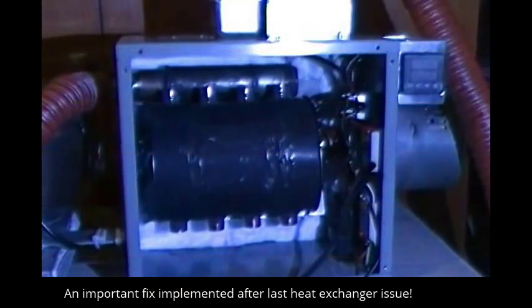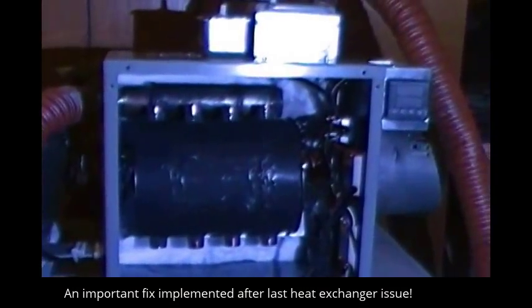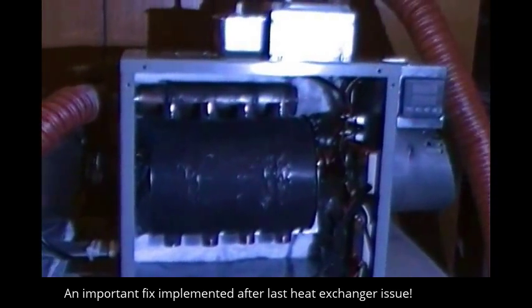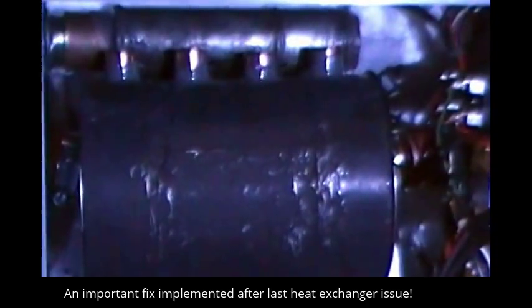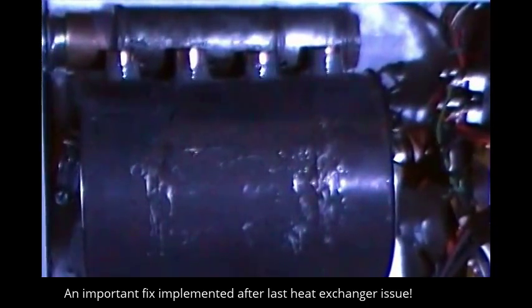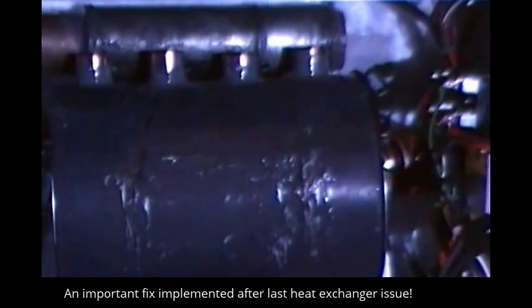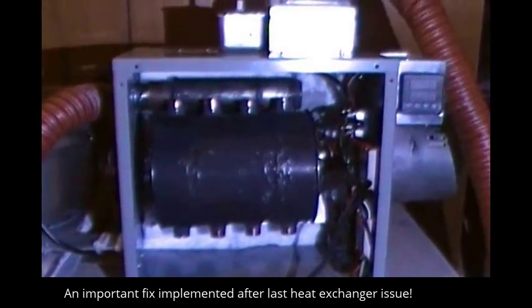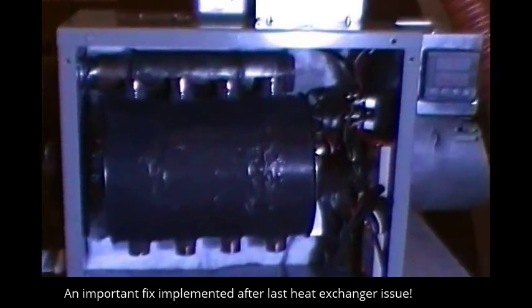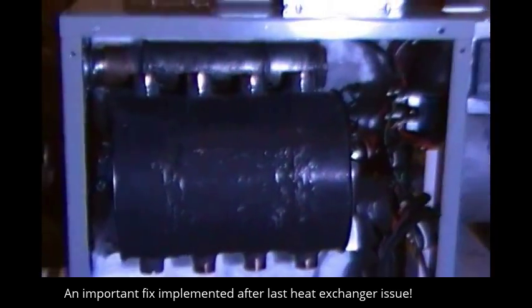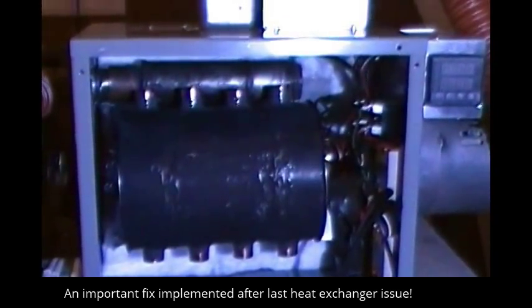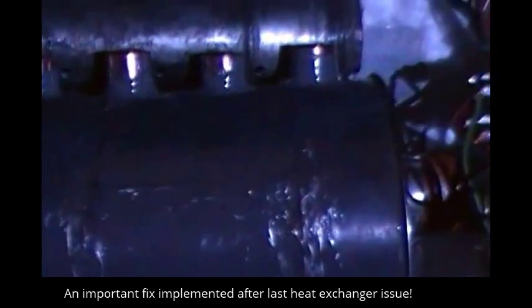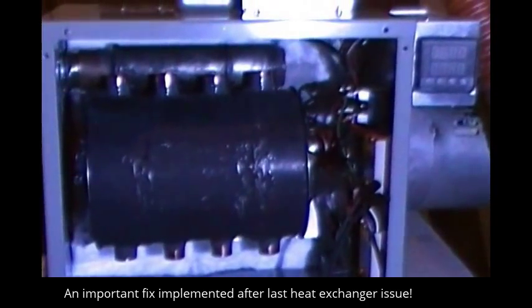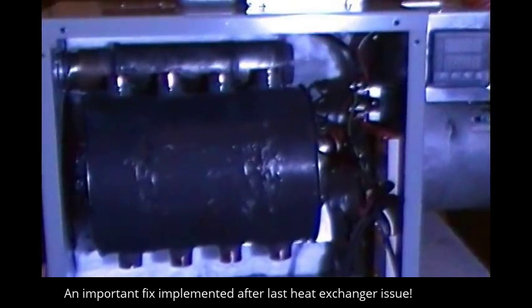Hi, this is Len and Cara from Coffee Roasters Club. After doing a test, we found that the initial heat exchanger we put inside the roaster, meant to pull heat off the exhaust and back into the fluid bed roaster, was not the best design. It was too intricate, the tubing was a little too small, and it didn't stay together correctly. So we made a less glamorous looking design, but I think it'll be more functional.